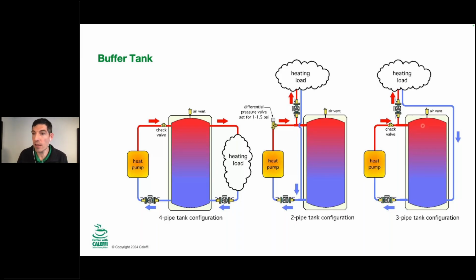Is that a good explanation for what you had in the shop in Missouri there? Yeah, I mean, that pretty much explains it. It's called direct to load piping. So if both the load and the boiler are putting out the same GPM, nothing goes through the tank. So that's the nice thing about it. And then when all the zones go away, the tank charges up. You charge the battery.